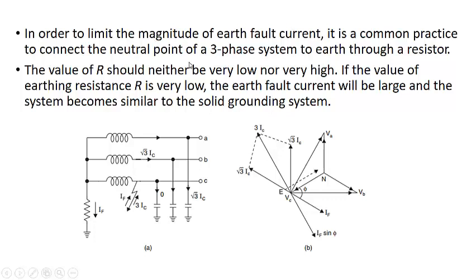It's a common practice to connect the neutral of the three-phase system to the earth through a resistor. The value of R should not be very low. If it is very low, it becomes close to a solidly grounded system. Nor should it be very high, because then it becomes close to the isolated neutral system, since a high value of resistance may only be considered an open circuit.